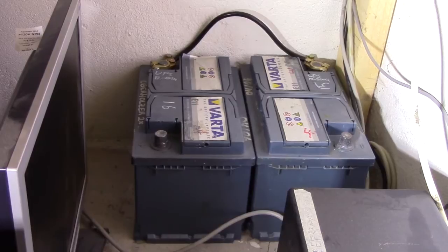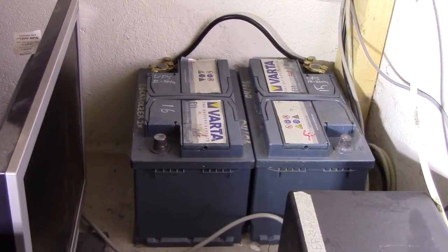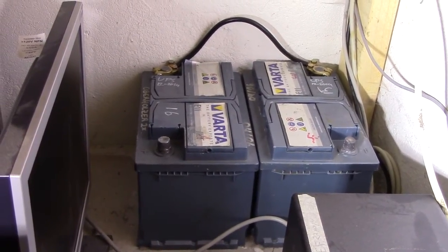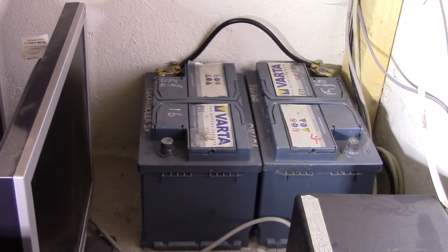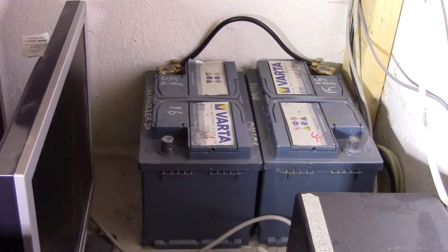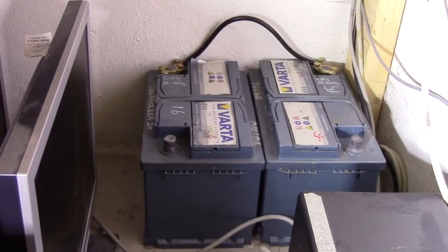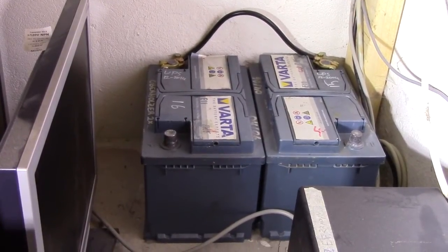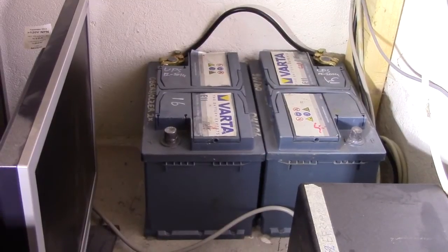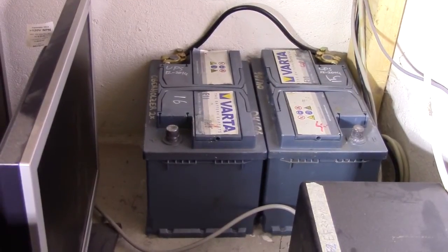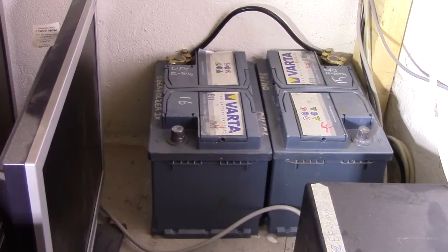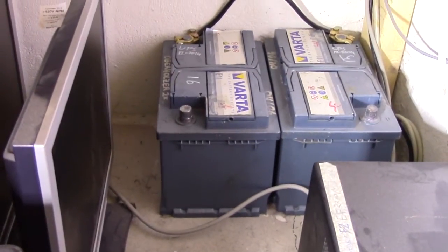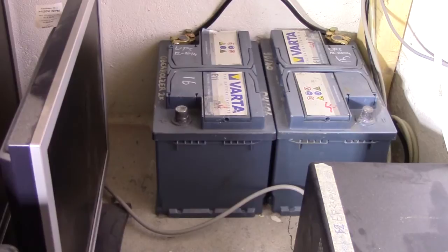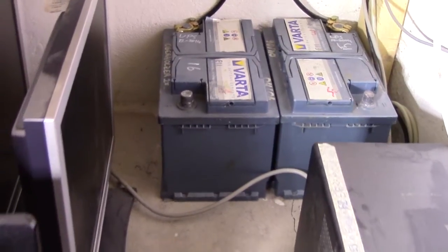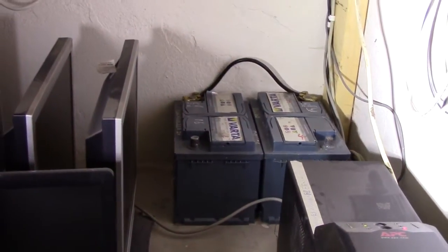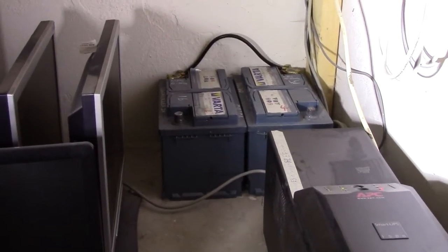And these batteries, while being in basically new condition despite their age, can only do perhaps 30 amp hours at the 30-ish amps of load that this UPS draws on the high load. So they might have better applications elsewhere. They are starter batteries after all, and above all they are flooded, so it's not really optimal to have them as UPS batteries when I have better options. So, time to get to it.